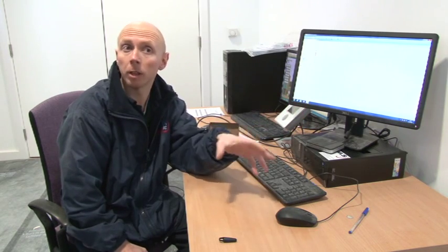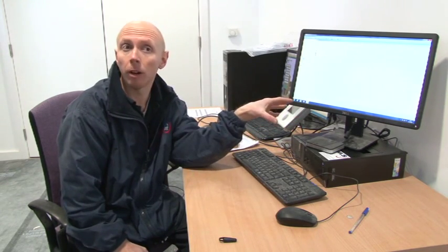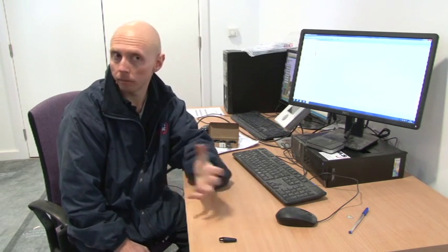The client wants to know whether you can use this system remotely, and that can be done. It just needs to be connected onto the building's network and allow port forwarding on the router, and then you can set up Paxton software on a remote machine anywhere in the world. And you can add tags and connect to the system and configure it remotely. But as I say, none of that's been put into place yet, but it can be done.